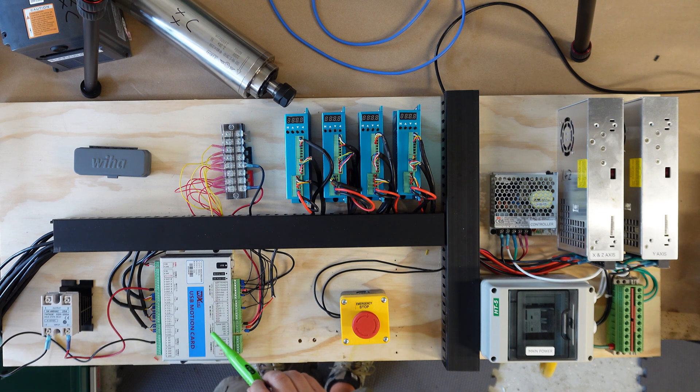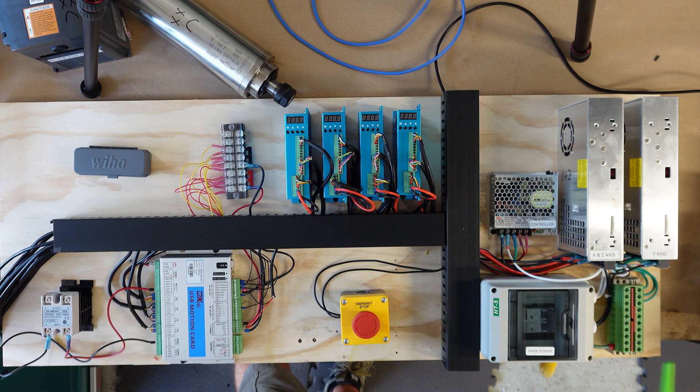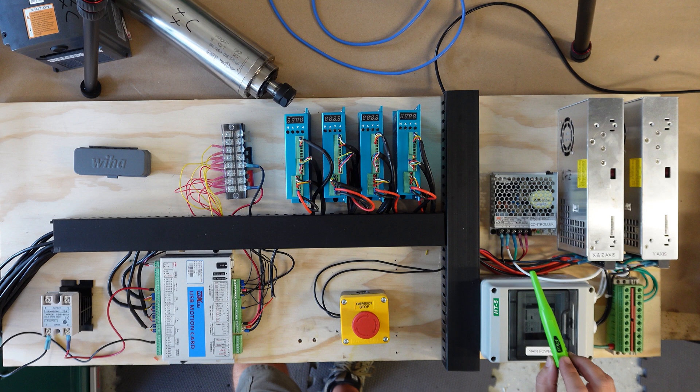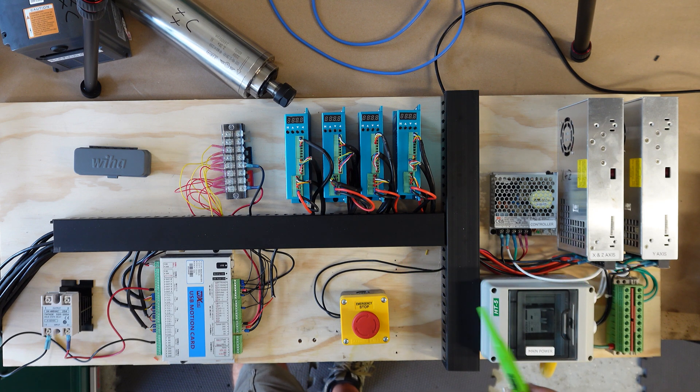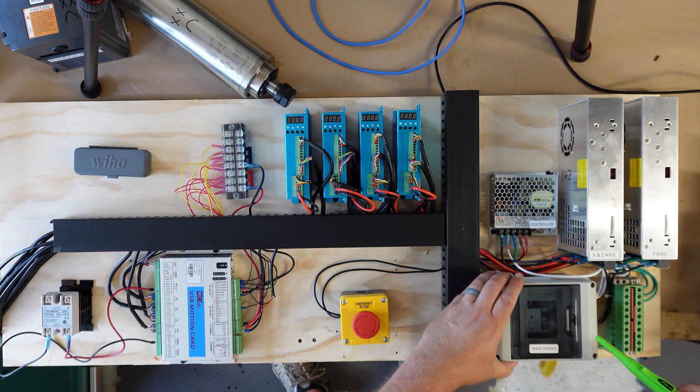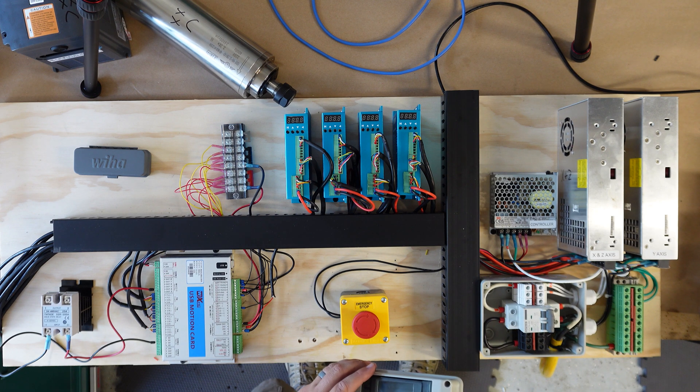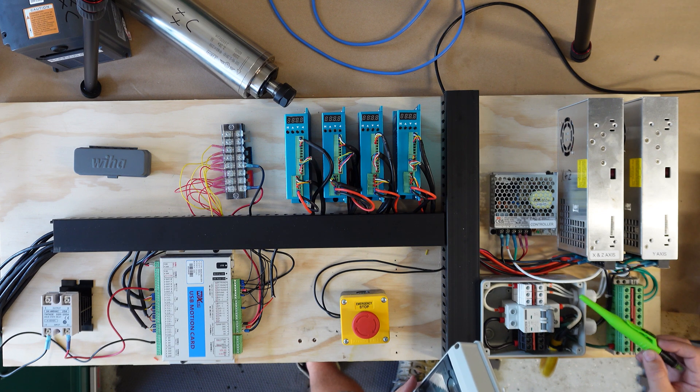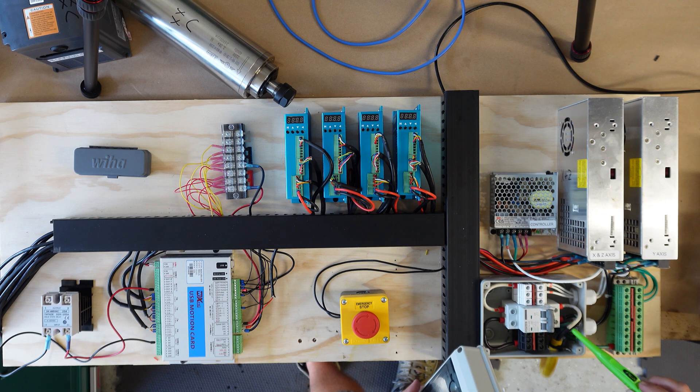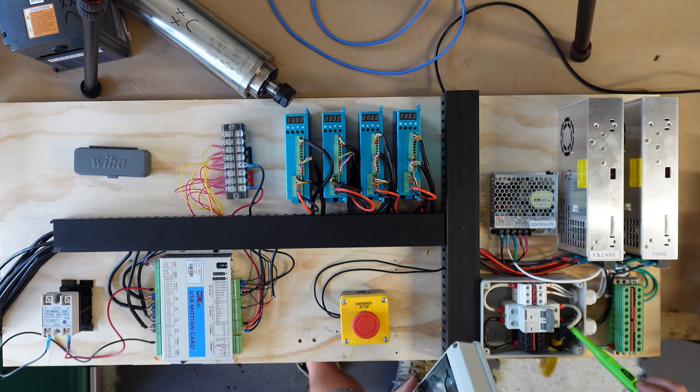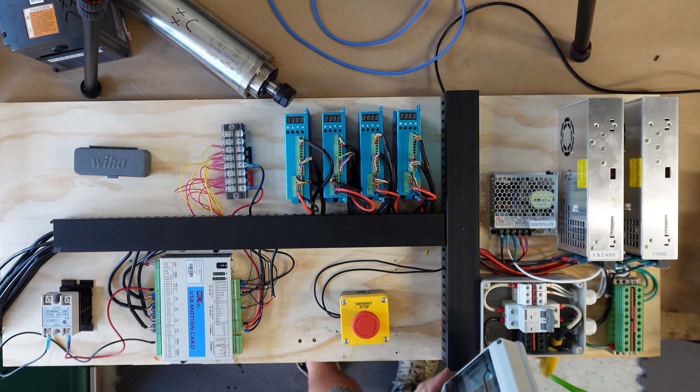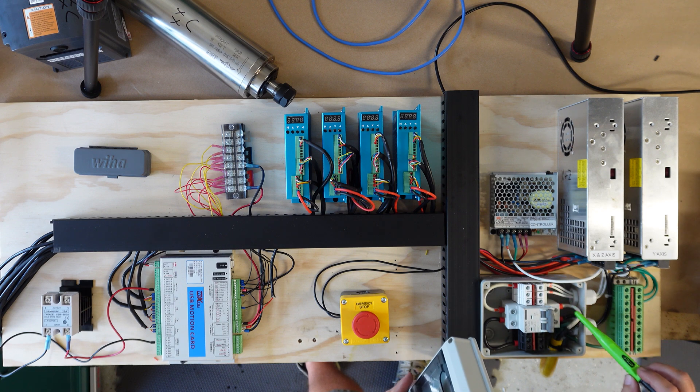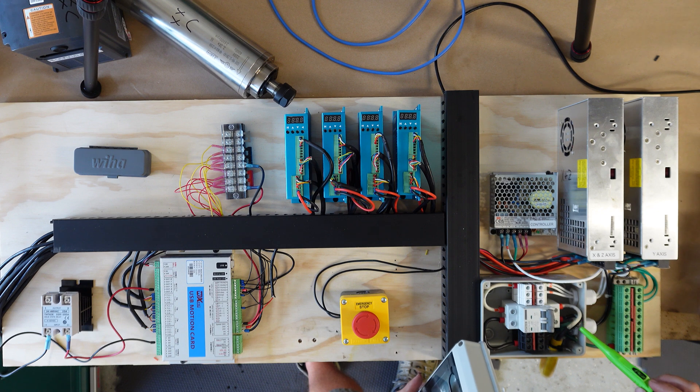Again, my goal was to see if I could get this particular controller to work. I actually have this running. I haven't cut anything with it, but all my limits are working. And we'll walk through that in another video. But I'll start by how I wired this. I created schematics for this as well. So as I'm walking through that, I'll post those. But we'll start with the power distribution. So I have my main power coming in. So this is actually an old boat shore power cord. I am running this at 220, 240 volt, whatever it takes. In the U.S., that would typically mean that you've got two live lines. So L1 black, L2 is typically red.